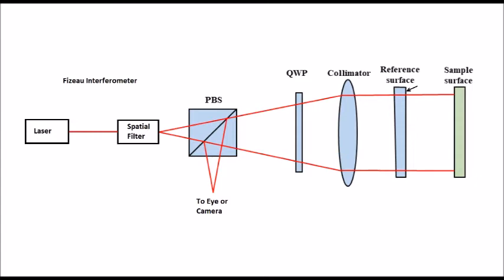Here's the basic layout of a Fizeau interferometer like my Zygo. A polarized laser goes into a spatial filter which cleans up and diverges the light, next into a polarizing beam splitter and a quarter wave plate, and then on to a collimator for a parallel output. For testing flats, a transmission reference flat is used—one reflection from the reference surface and one from the test part, reflected back into the collimator, passing through the quarter wave plate again.